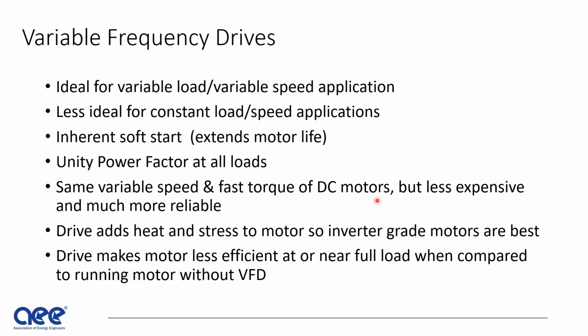Unity power factor at all loads, same variable speed and fast torque of DC motors. In fact, it's better than DC motors, but less expensive. The drive does add heat and stress to the motor, so that's why inverter grade motors are best. Drive makes the motor less efficient. Remember that whatever efficiency you have in the motor, when you've got a VFD, you've got about a 3 to 4% efficiency loss in that VFD. That adds to the overall efficiency of the system.